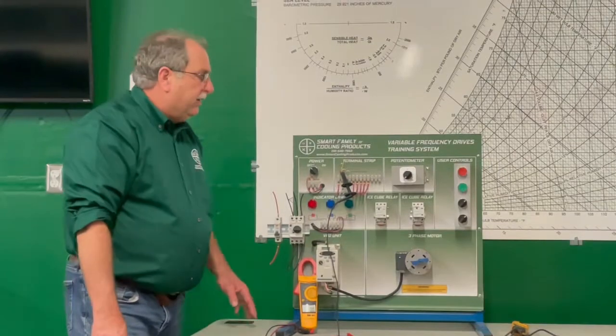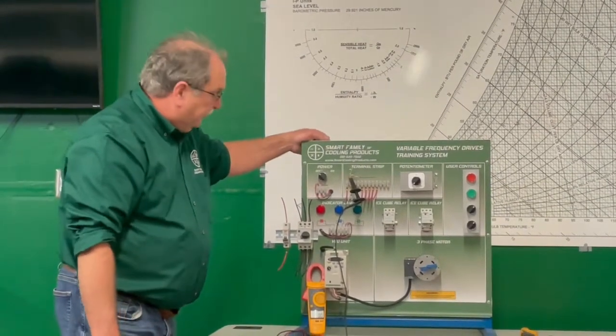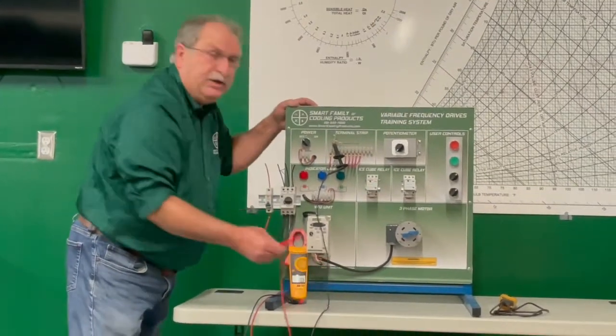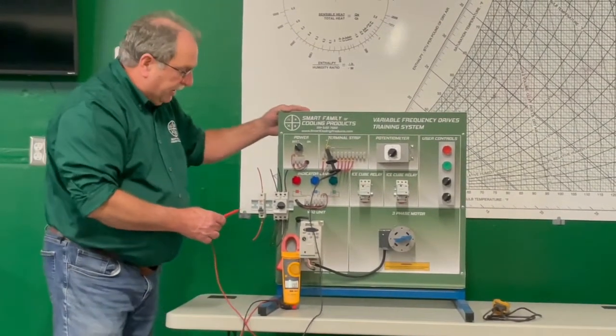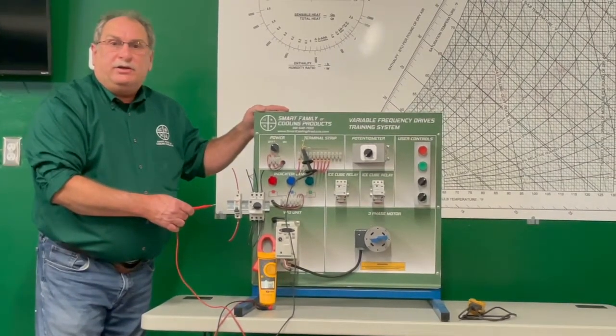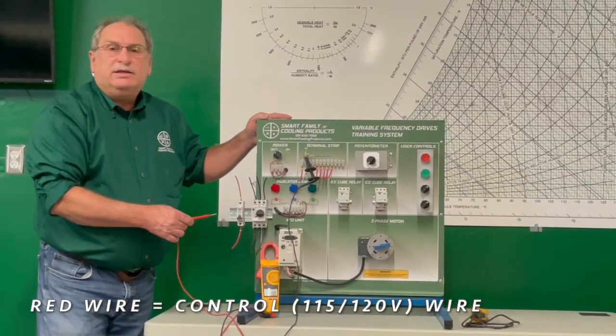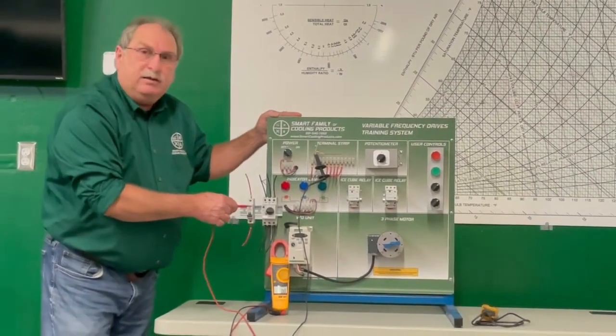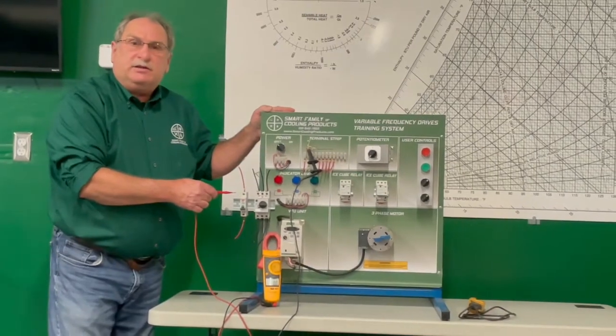So when you're using a meter, you always want to check for power on a known circuit. In this case, on our units, we use red wire to indicate the control circuit voltage. Typically, that's 115 volts.